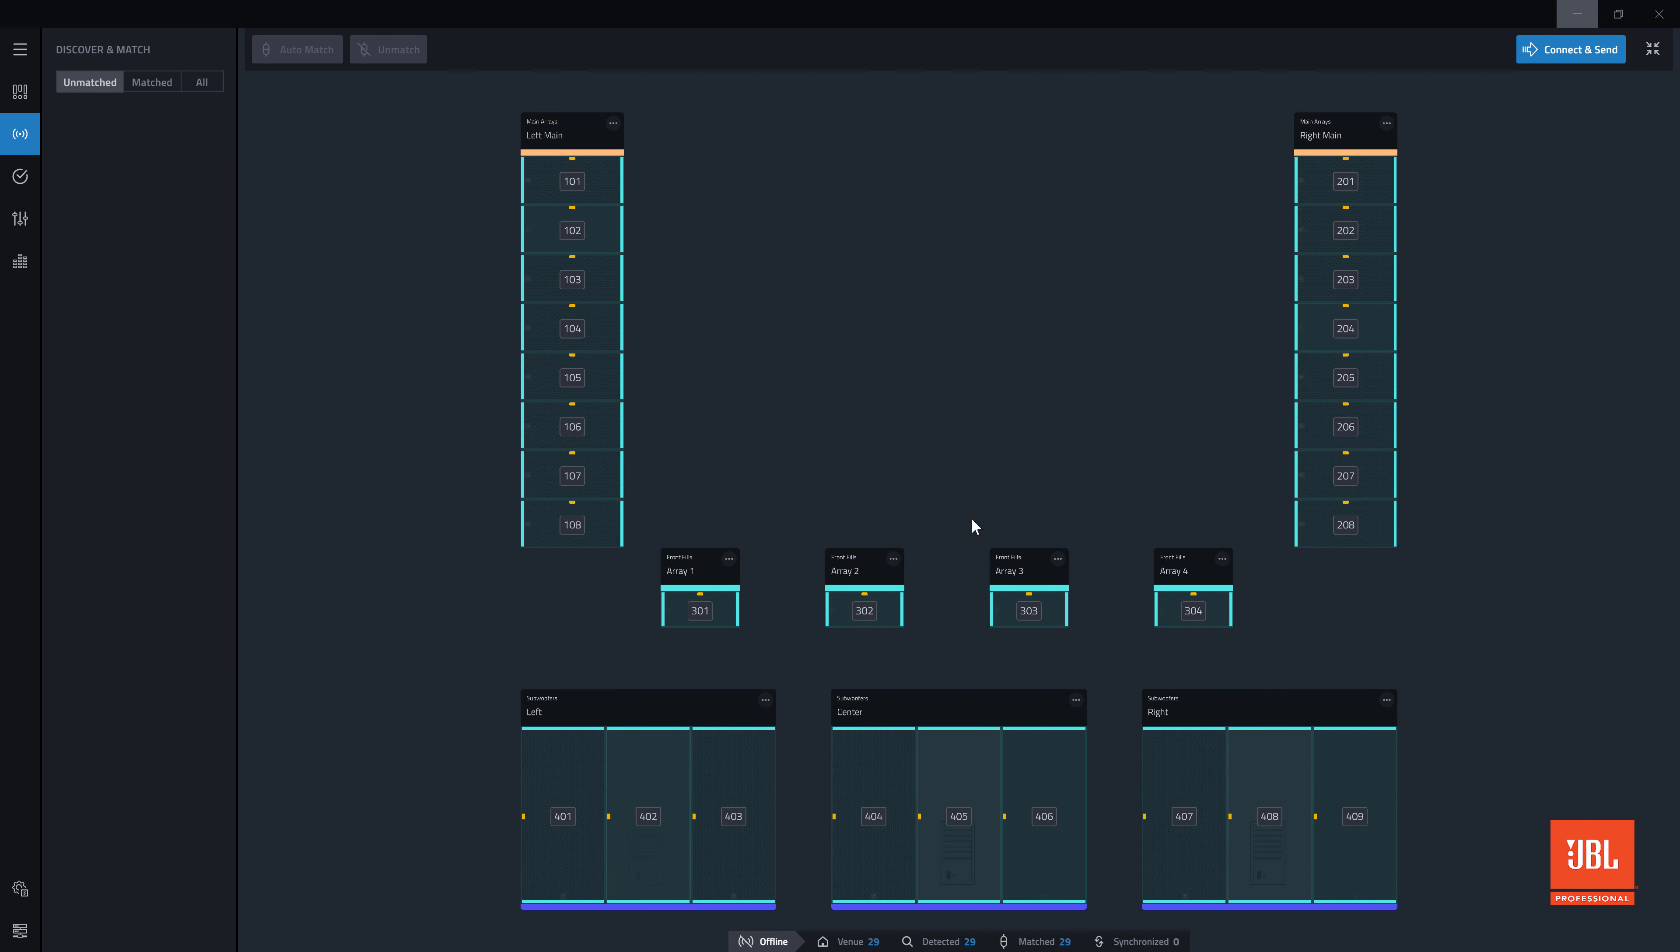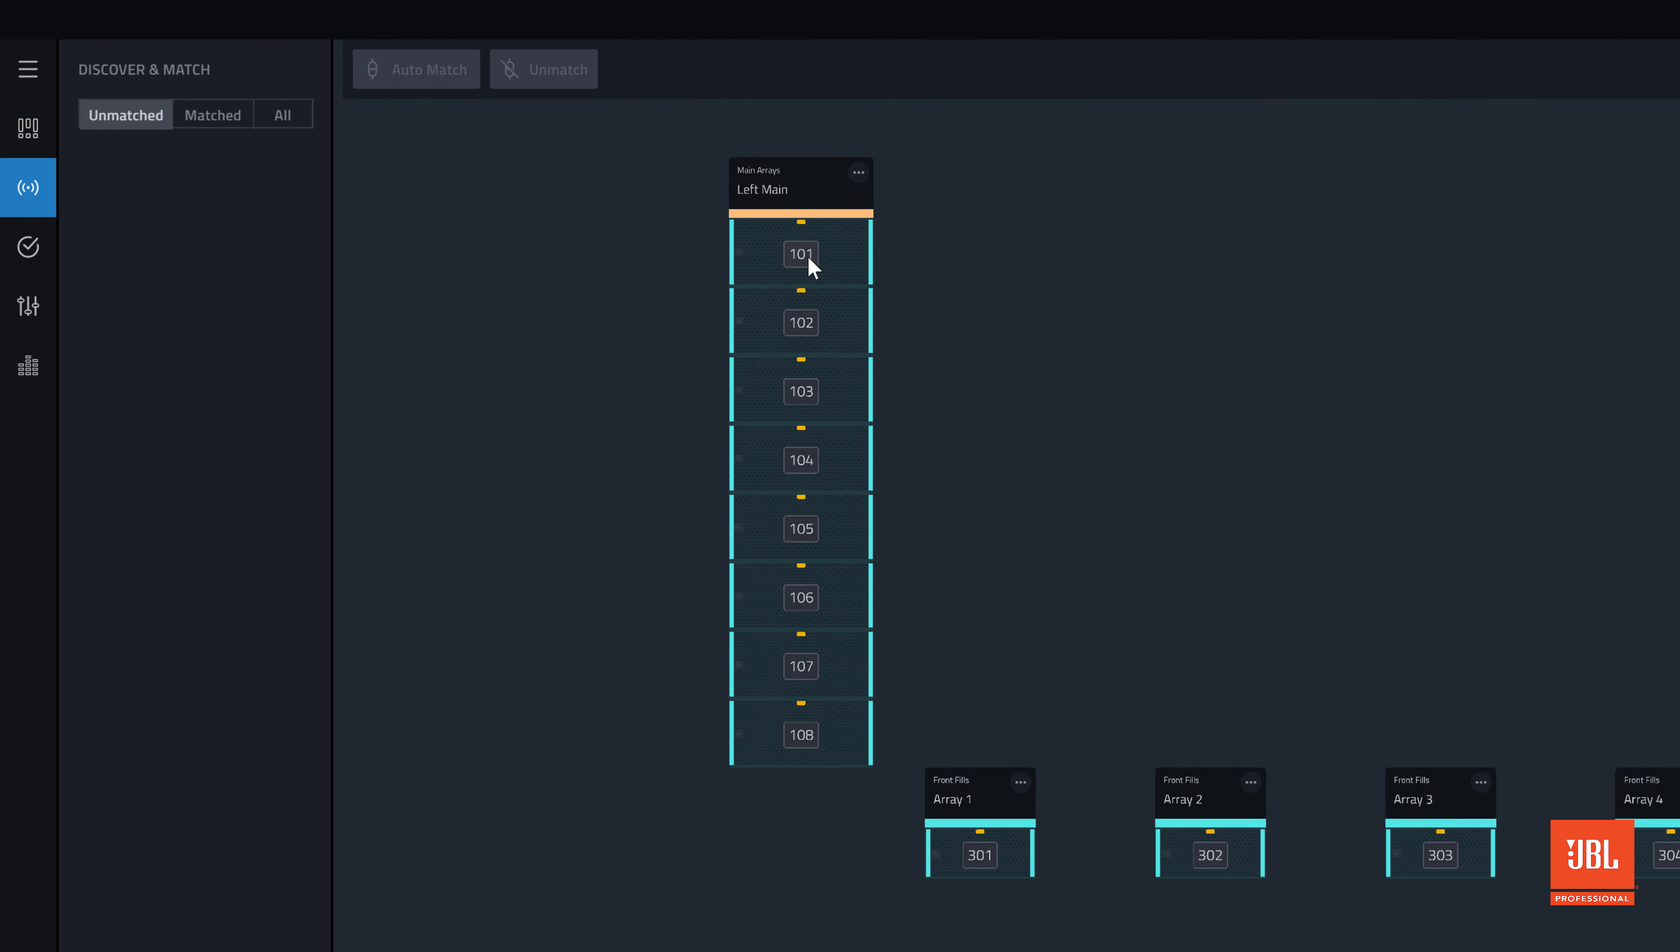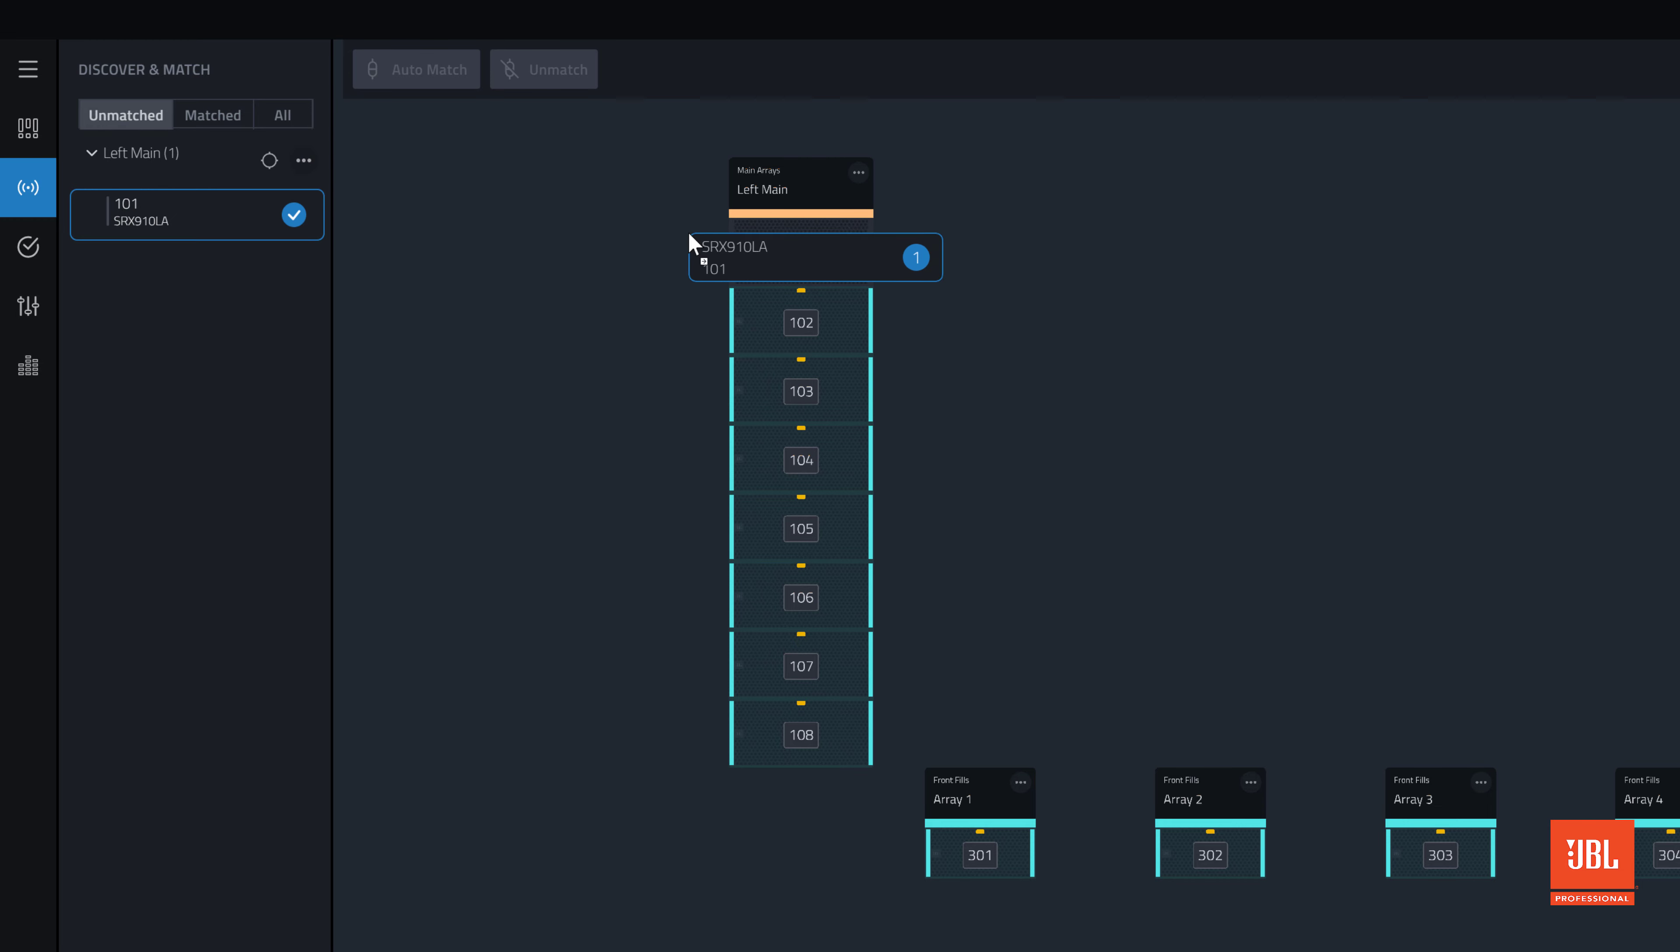We can now see that all the devices in the design have a yellow light to indicate they have been matched but are still offline. If a change is made to the container or HCID in this state, the device will be unmatched and will show back up in the discovered column with its original ID because the virtual device no longer matches the physical device.